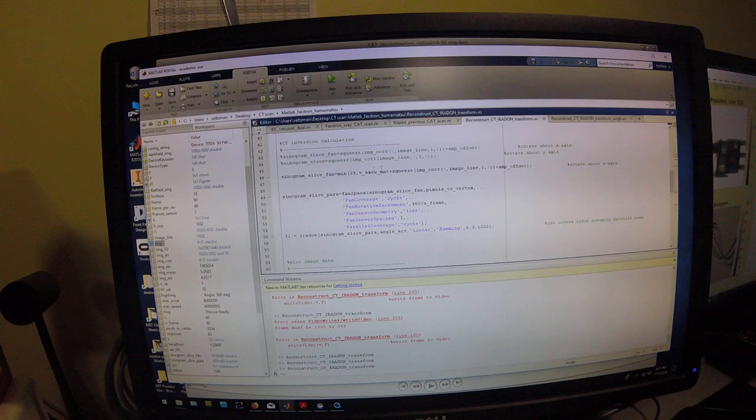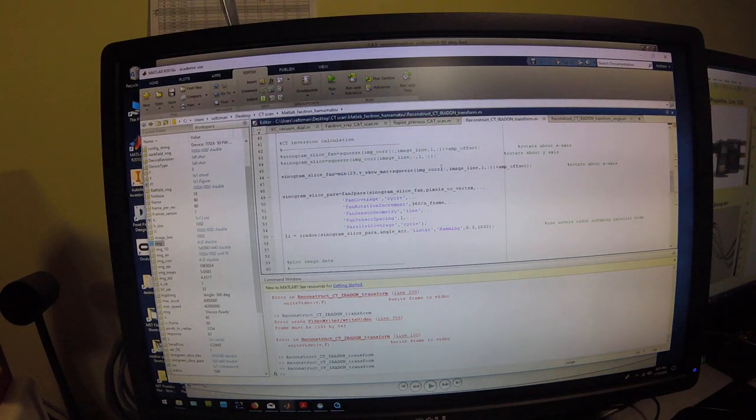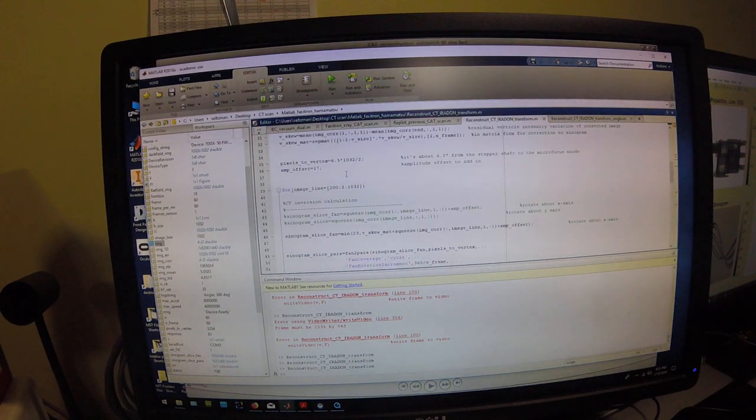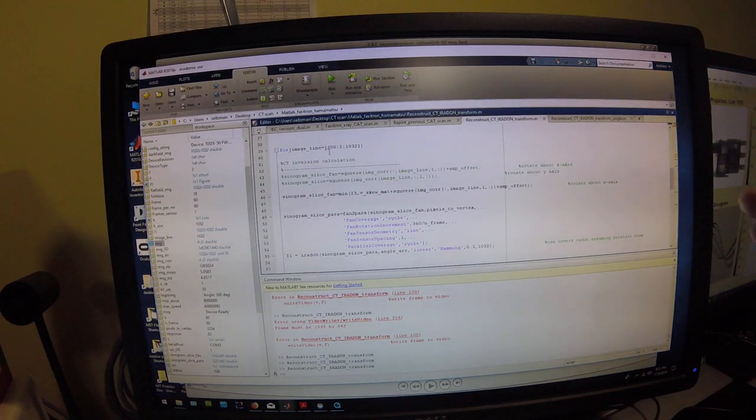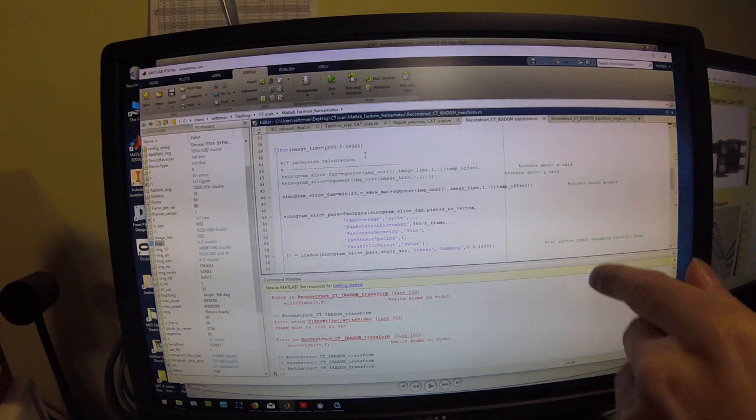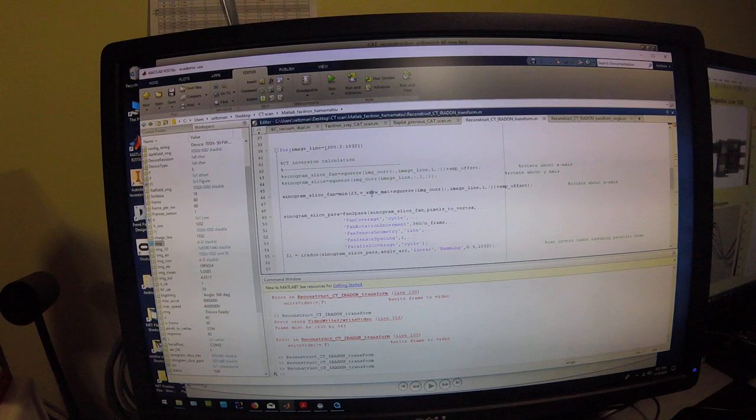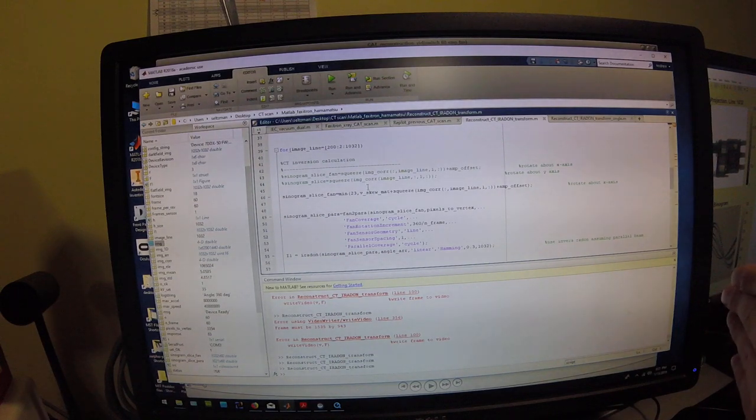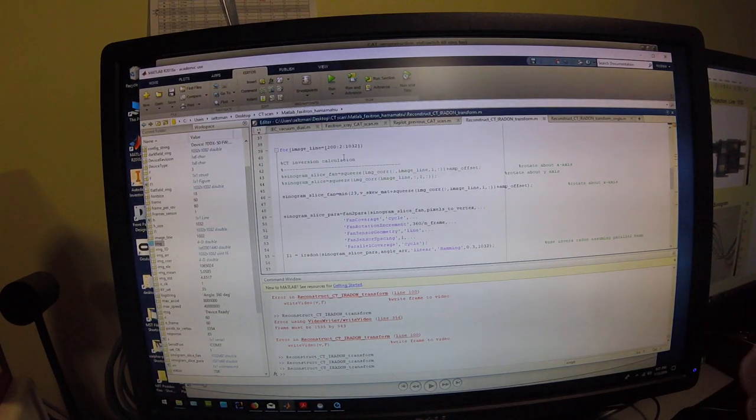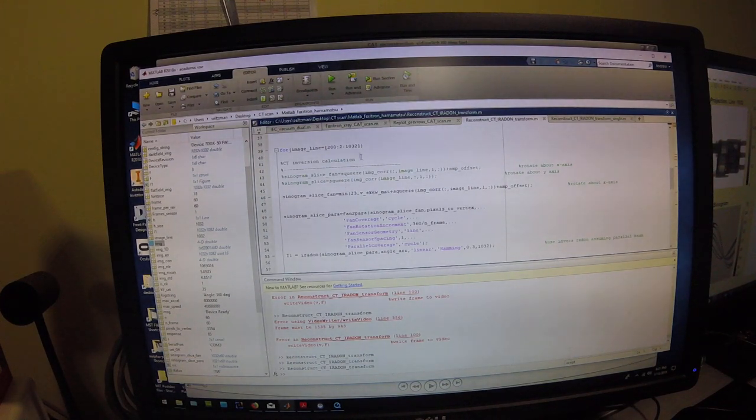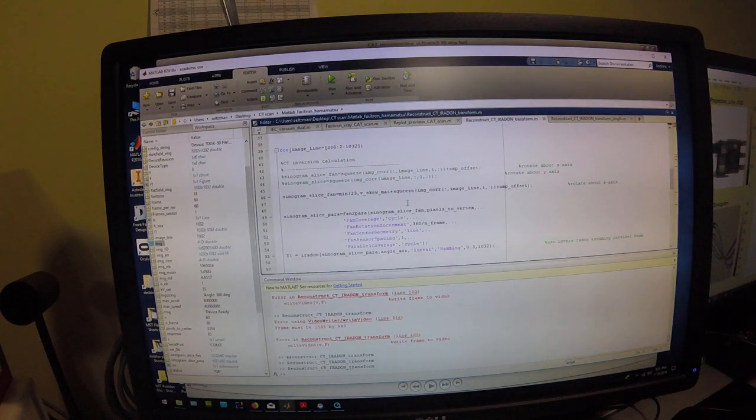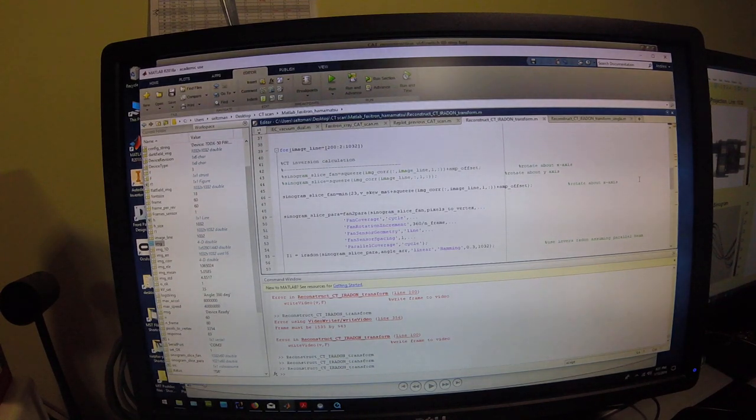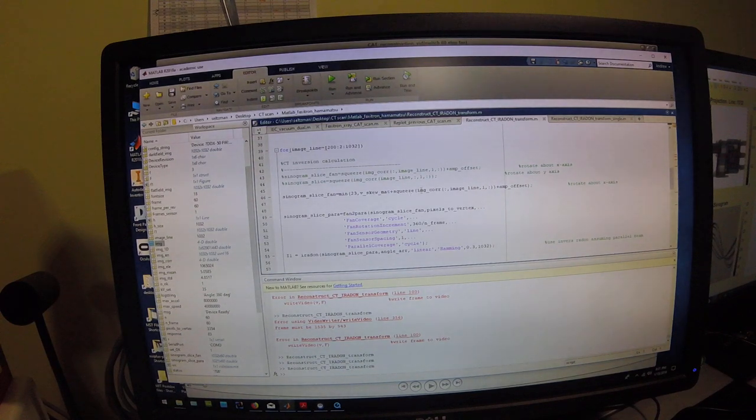Then, it's going to generate a sinogram and it's going to start stepping through each vertical line for a given horizontal location in the image. In this one, this is a 60 frame reconstruction, so it's in 6 degree increments. So, it's going to generate a 1032 pixel vertical by 60 frame horizontal sinogram in 6 degree increment steps.